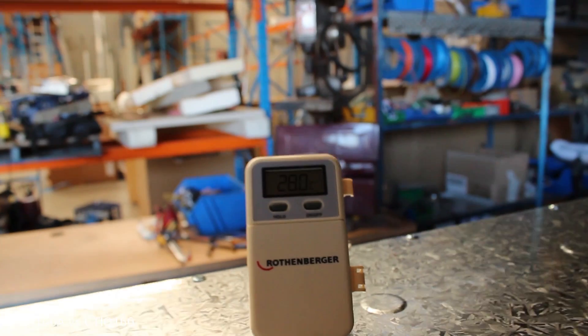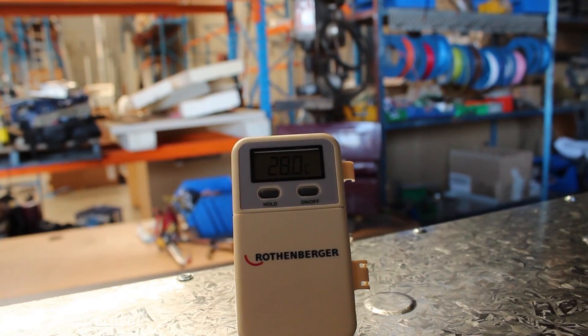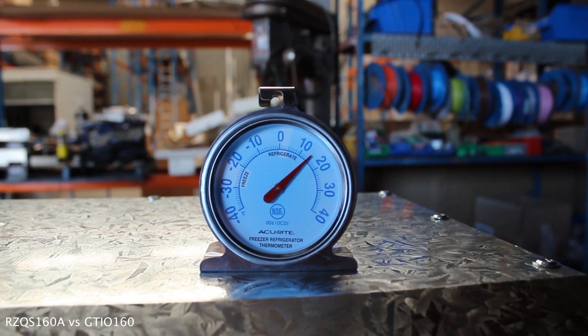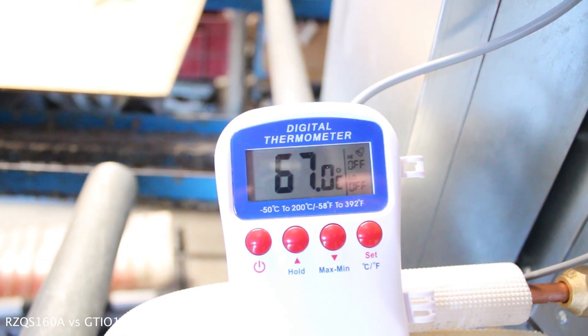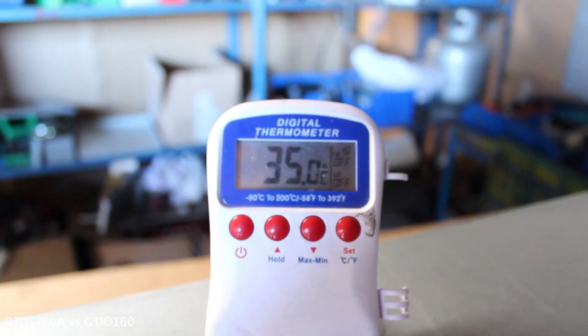What you're looking at here is the Daikin discharge pipe temperature of 38 degrees, and the Daikin's air-off temperature is 28 degrees. The ambient temperature in the room is about 15 degrees. The Pioneer Inverter's pipe temperature is 67 degrees, and its supply air temperature is 35 degrees.